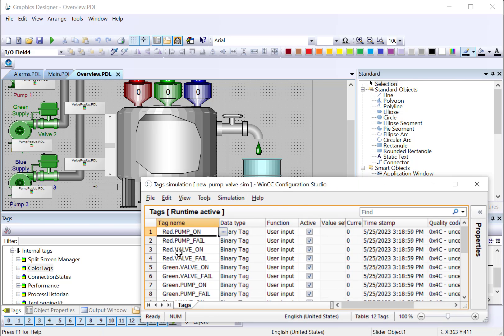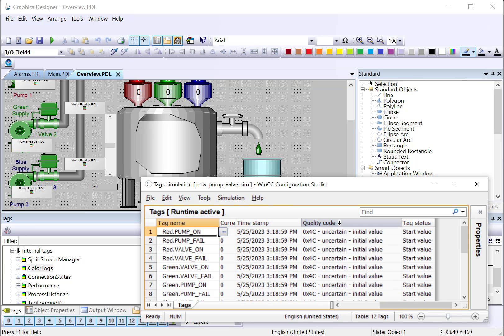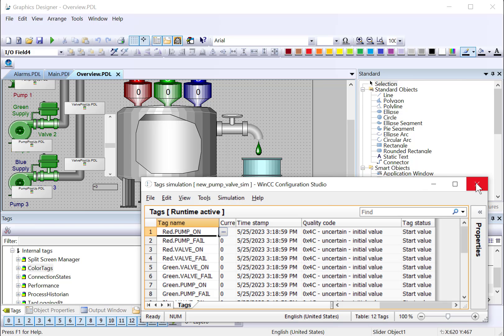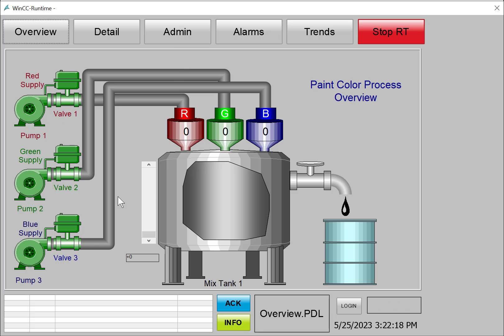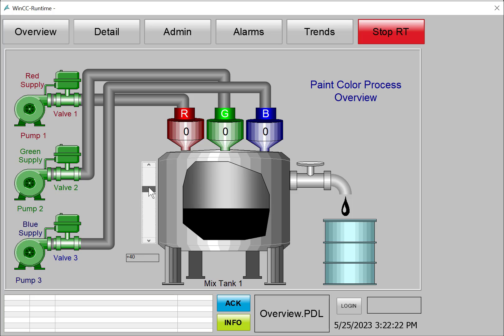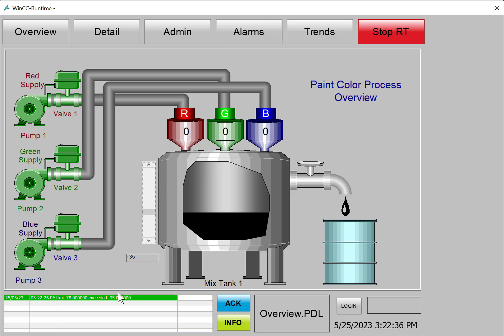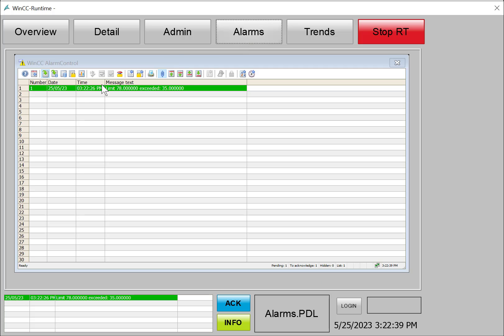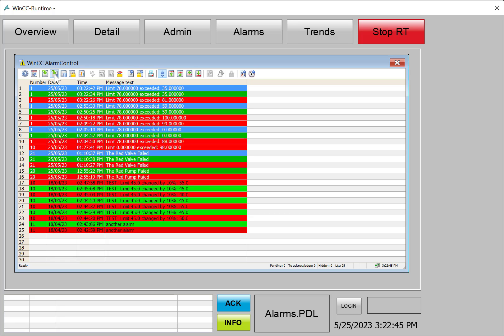You may ask why we're not using the Tag Simulator to change the level to generate the alarm. And it's because the simulator gives all the tags it's keeping up with an uncertain status. And the alarm service doesn't recognize it as a valid value. And it will not trigger the alarm. So we can't use the Tag Simulator for this. So I'm just going to close this, save, and I'm going to refresh runtime. So as I change this and I get above our limit, then you see it has exceeded our limit. It generates the alarm. When we come back down into range, the alarm goes away. We can go to our alarm screen, select the alarm, and acknowledge it. And we can go back to our history and see the history of these alarms.